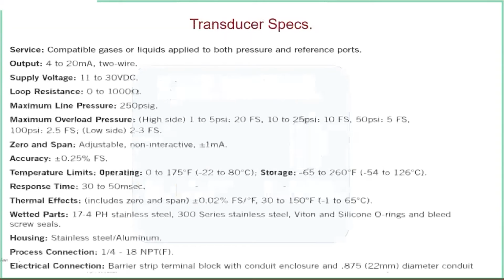Then some of the transducer specs I put in here, some of the main ones: this is a stainless steel transducer, made out of 300 stainless. Something else important is it'll work anywhere from 11 to 30 volts DC. Of course we used 24 when we were out there. And then loop resistance is good from 0 to 1,000 ohms.